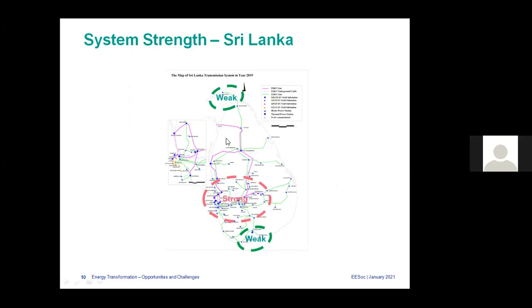But if you move away, you can see only one 220 kV line or 132 kV line towards the north, and a few 132 kV lines towards the south. So if you calculate fault levels, they will be much less compared to near the Western Province or in the hill country area. So from a system strength point of view, you will have weak system strength towards the south and north of the country.